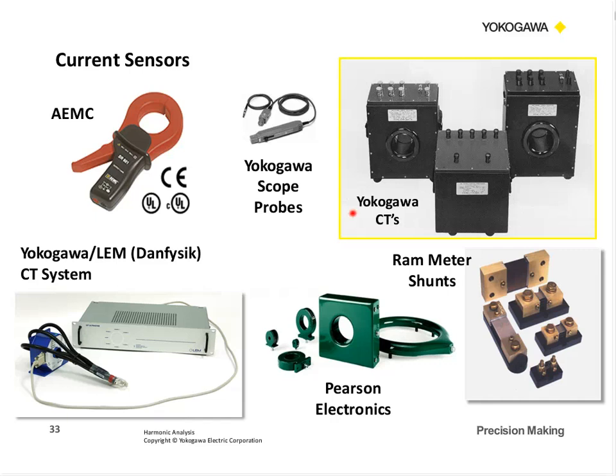We do make some of our own brand of potential and current transformers. These are good up to about 1,500 amps and about 3,000 hertz, and down on the low end about 30 hertz. Scope probes. Now, scope probes have a good bandwidth, and sometimes we like to use them, but you have to be careful using them on a power meter with the match of the instrumentation with the probe. We do work as a reseller from the AEMC, and they have some very good clamp-ons with some good bandwidth that we have selected as products that would be good for power measurement. And then Pearson Electronics, very popular in the lighting industry. They have good high bandwidth and medium accuracy.